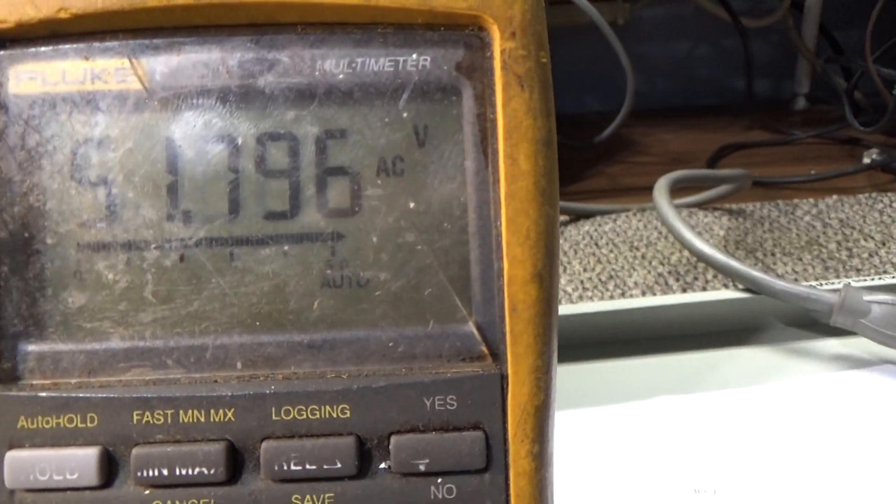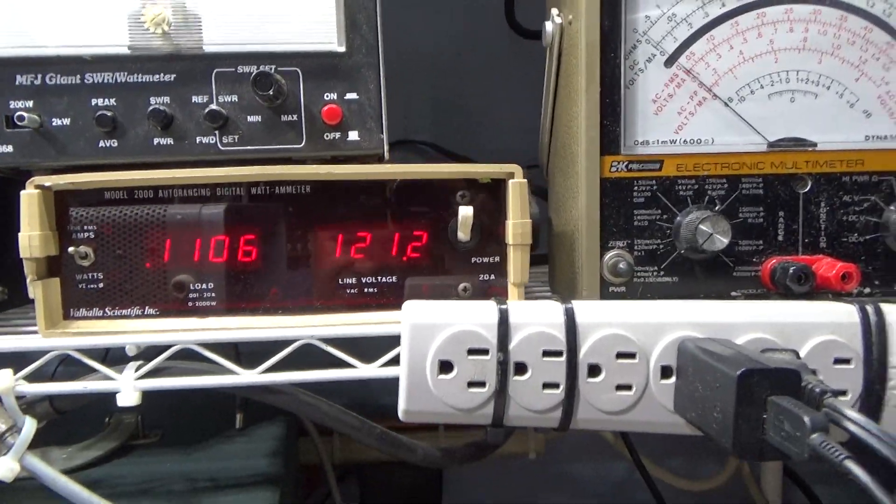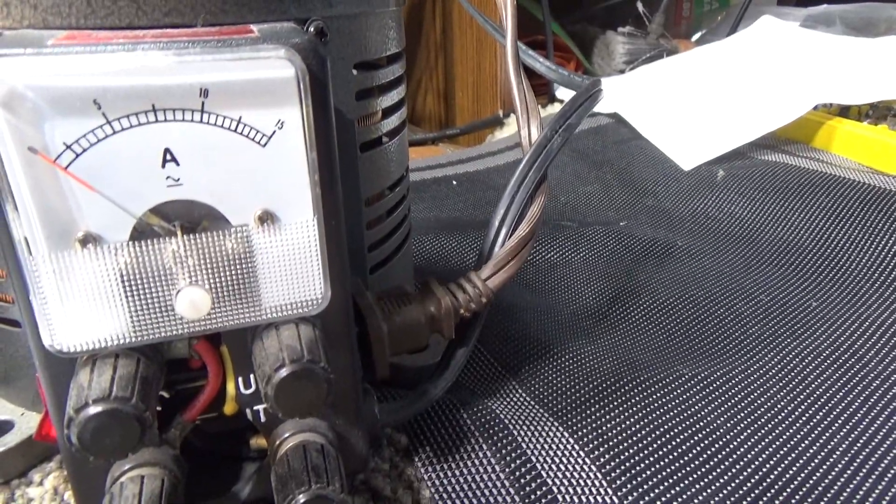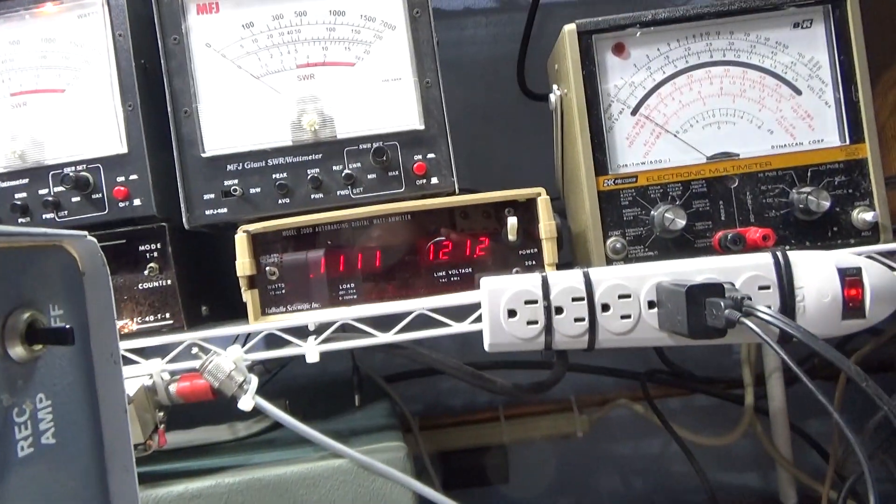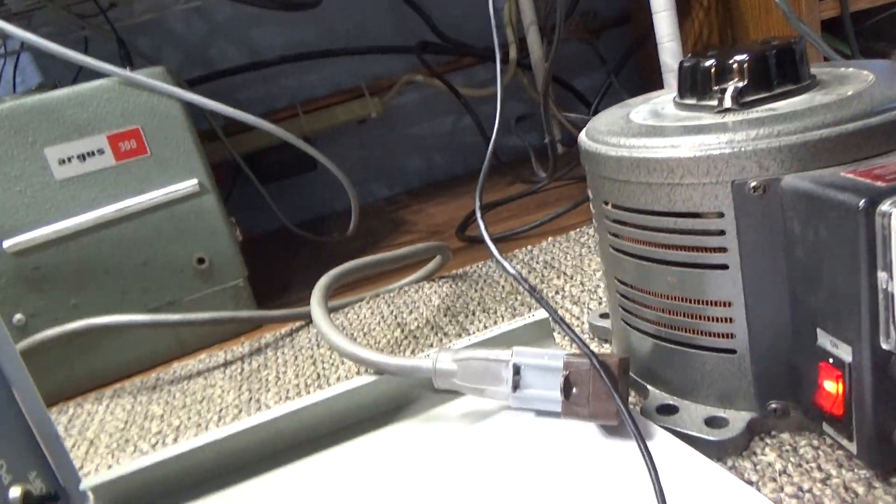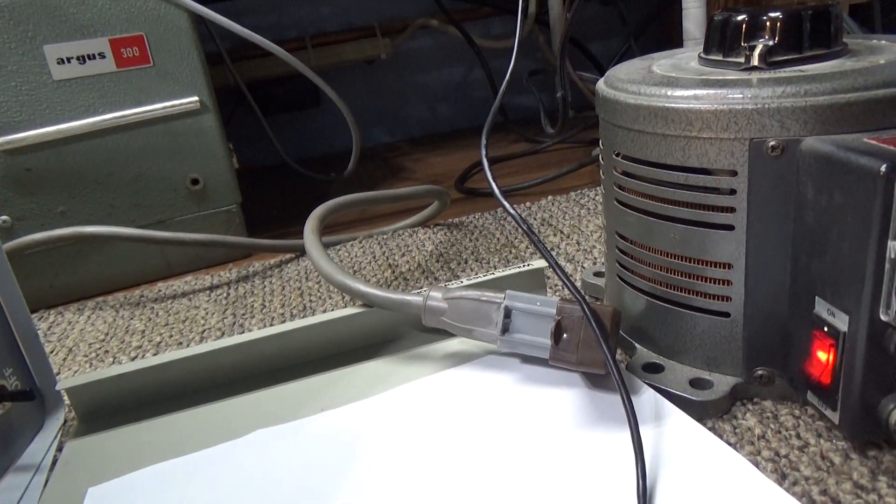Over here, 0.1 amps on that one, and this one is very barely moving. That's why I like the digital—I can get a better picture. It's not pulling high amps and the voltage is coming out right, so I have them wired correctly in the correct phase.